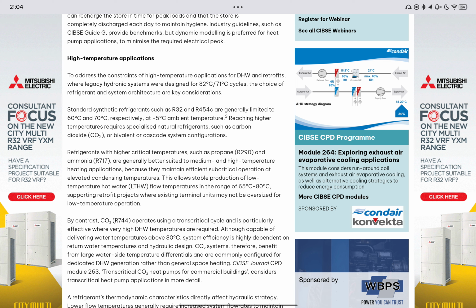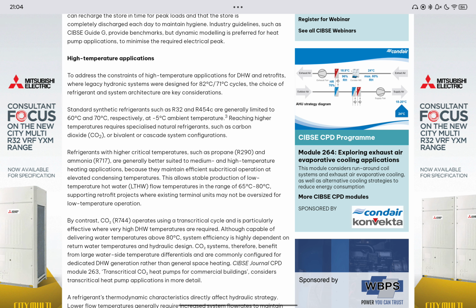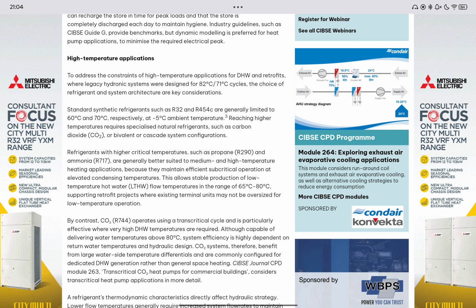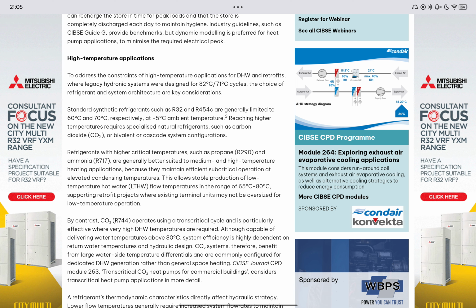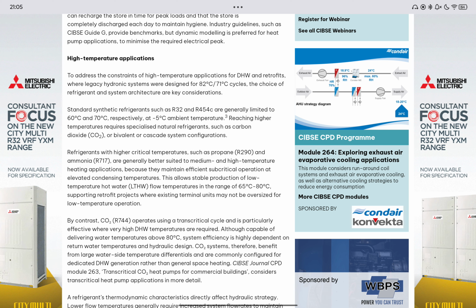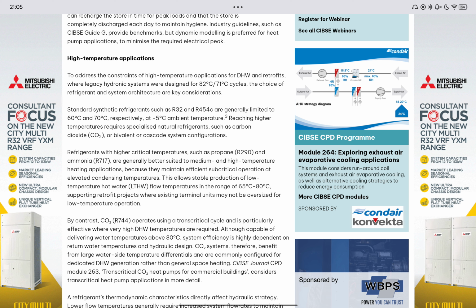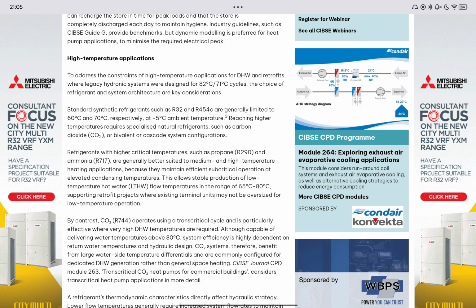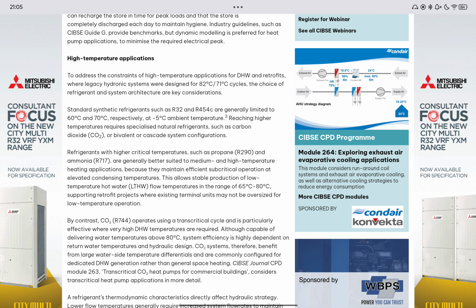Refrigerants with higher critical temperatures such as propane, or R290, and ammonia, or R717, are generally better suited to medium and high temperature heating applications because they maintain efficient subcritical operation at elevated condensing temperatures. This allows stable production of low temperature hot water, or LTHW, flow temperatures in the range of 65 to 80 degrees C, supporting retrofit projects where existing terminal units may not be oversized for low temperature operation.